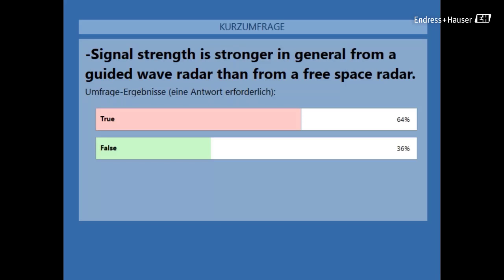Yes, Rob, go ahead. Please be careful with foam, guys. You can measure the foam when it's consistent from an electrical property, a dielectric constant perspective. Now how often is that the case? So it's probably better to set it on the signal-to-noise strength of the reflection signal coming from the foam, and then you can roughly determine how much foam you have, but it's more to control your anti-foam in that case than to know exactly how much is in it. This is something you really have to set to your process and application, it's nothing we can say from the factory will just work, you really have to know your process and the foam you have in that specific application. But a good question, very good question.